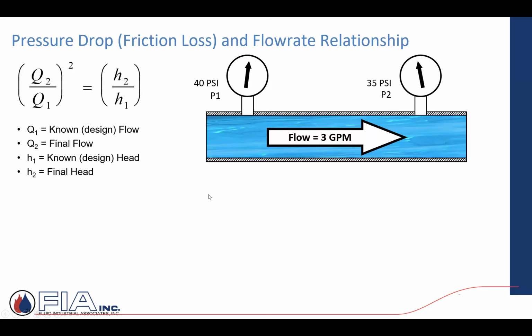If I want to change the flow through that same coil, I know what the new pressure drop is going to be. It's going to be less if I reduce the flow, and more if I increase the flow. A lot of times in the industry they say, if you double the flow, you're going to double the pressure drop. It's a direct relationship. But if you look at that formula, it's not. What they're trying to show here is a change in flow, whatever that relationship is, square that answer, times your original design head. So the change in flow, the resulting pressure drop is a squared relationship.